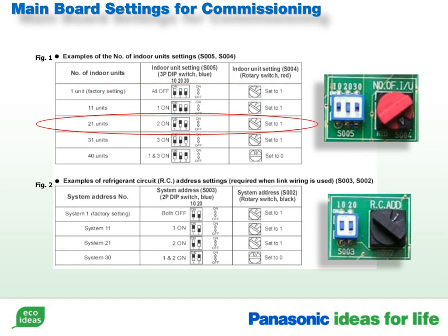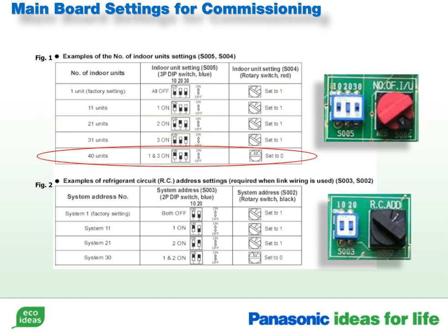If you have 21 units, you would set dip switch number 2 to the on position and set the rotary dial to 1. If you had 40 indoor units, you would set dip switch number 1 and 3 to the on position and the rotary dial to 0.